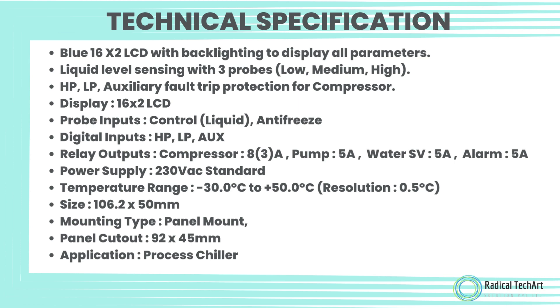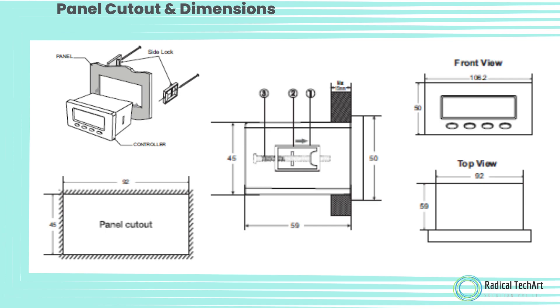Relay output ratings: Compressor 8 (3) Ampere, Pump 5 Ampere, Water SV 5 Ampere, Alarm 5 Ampere. Power Supply: 230 Volt AC. Standard Temperature Range: minus 30.0 degrees Celsius to plus 50.0 degrees Celsius. Resolution: 0.5 degrees Celsius. Size: 106.2 by 50 mm. Mounting Type: Panel Mount. Panel Cutout: 92 by 45 mm. Application: Process Chiller.